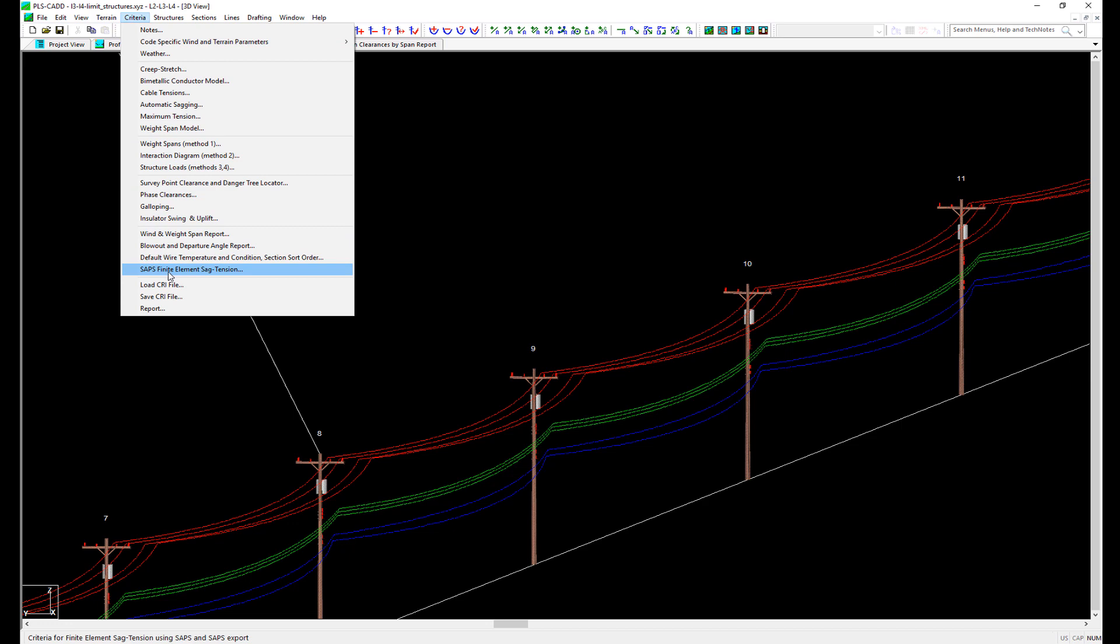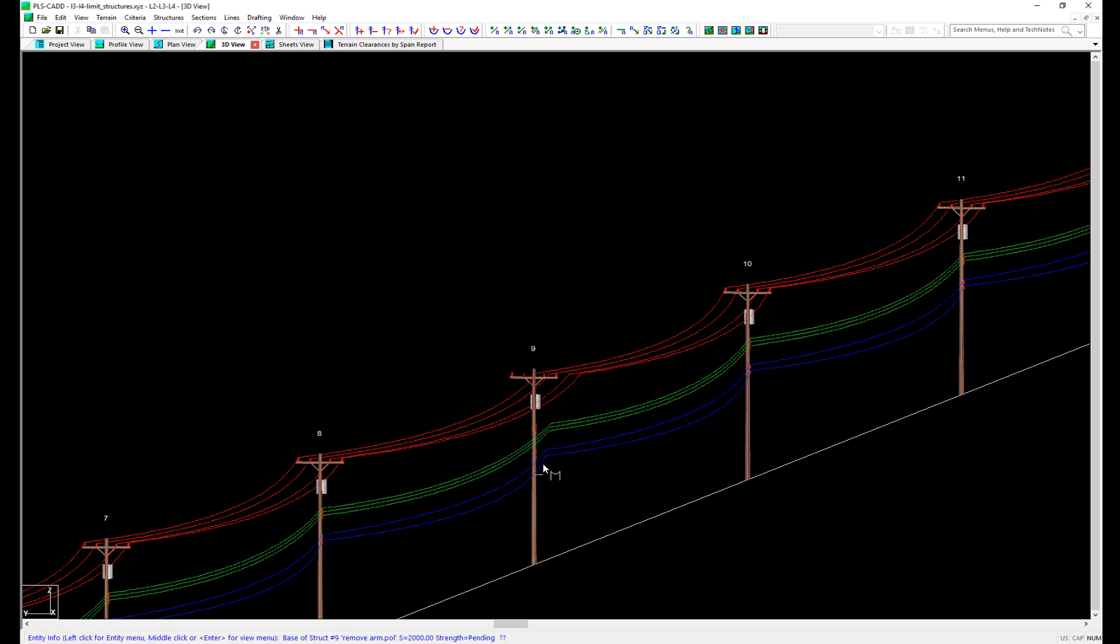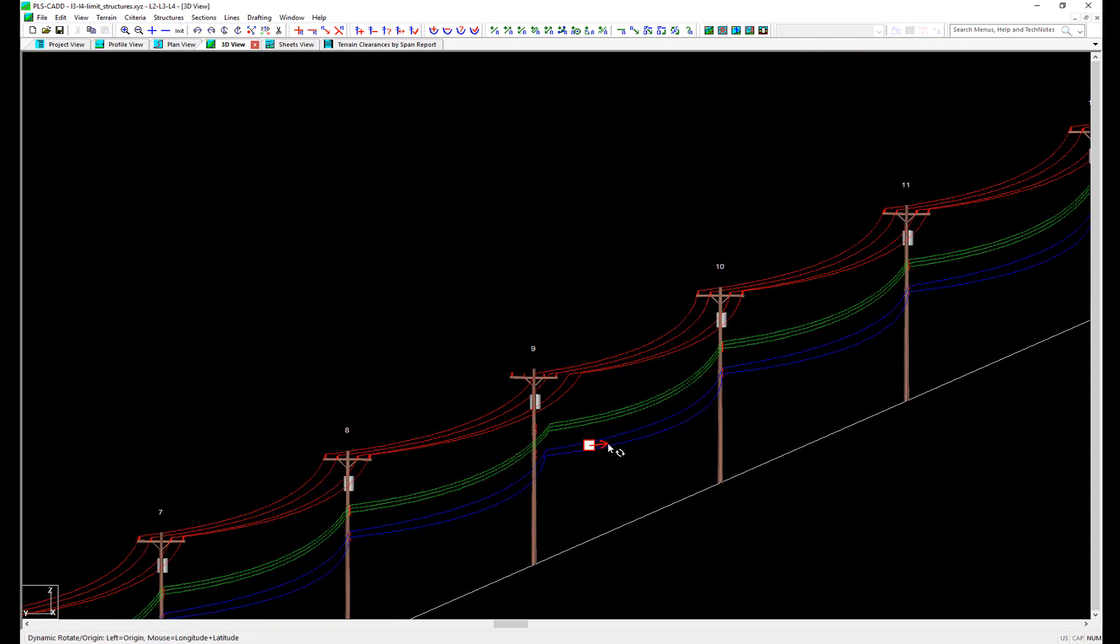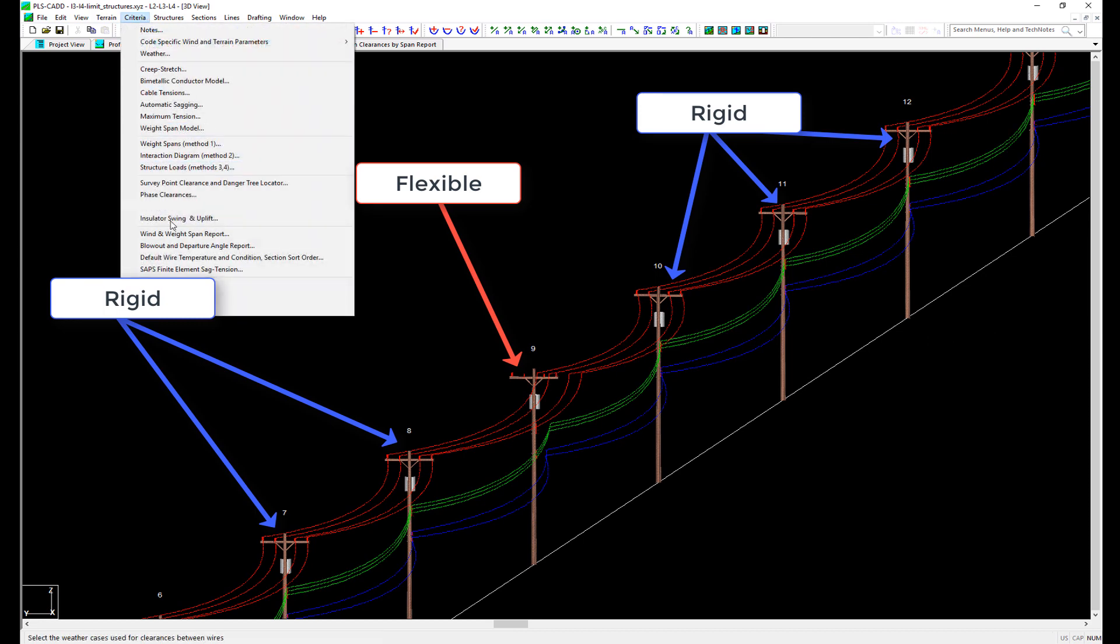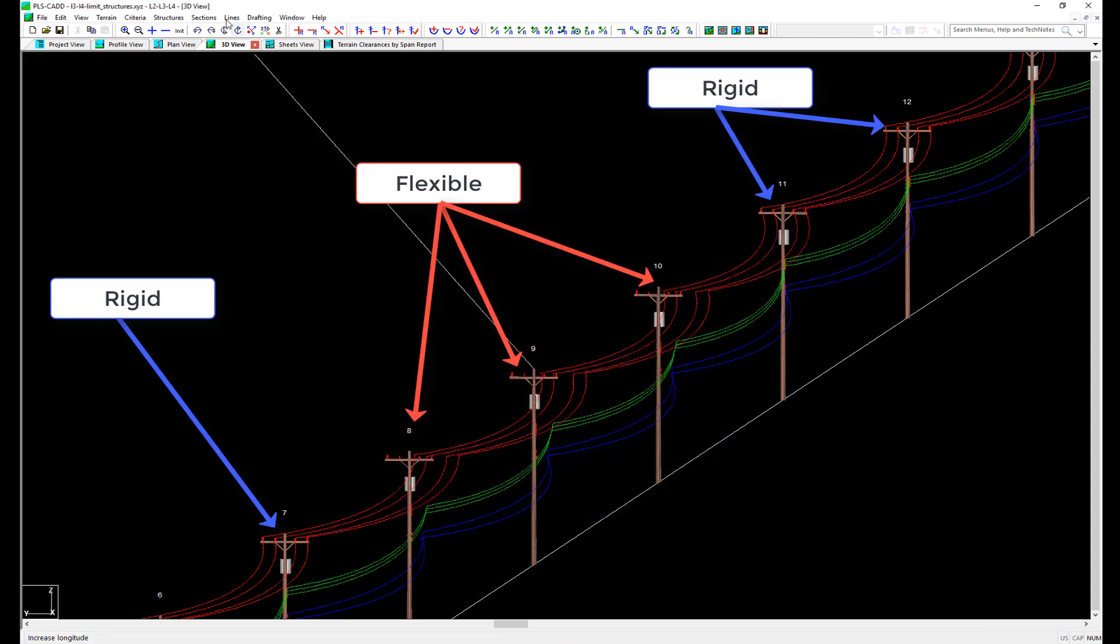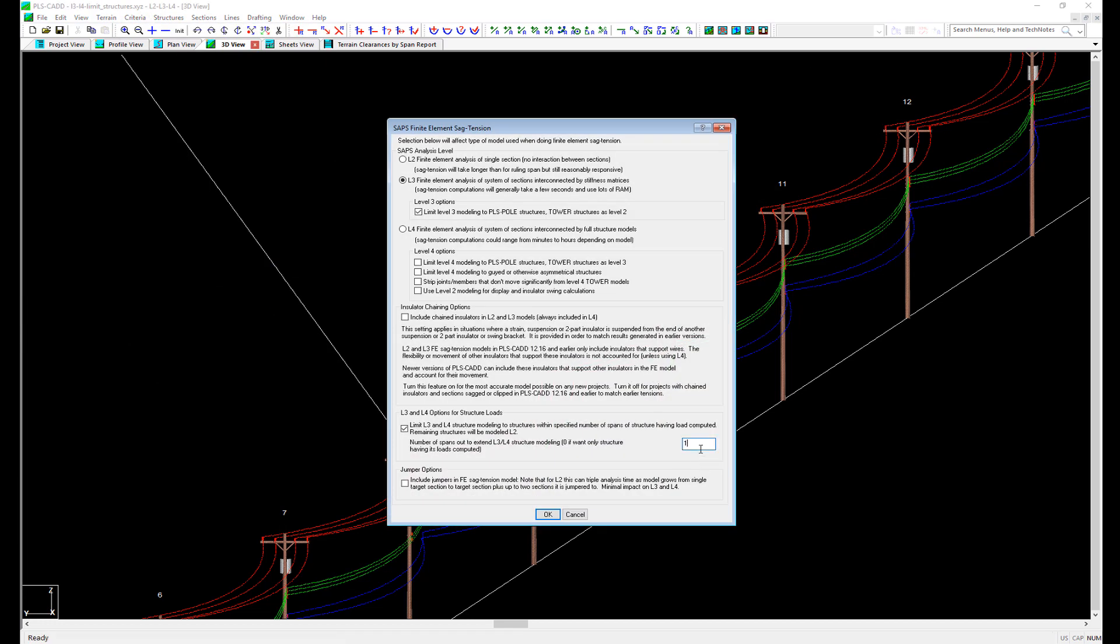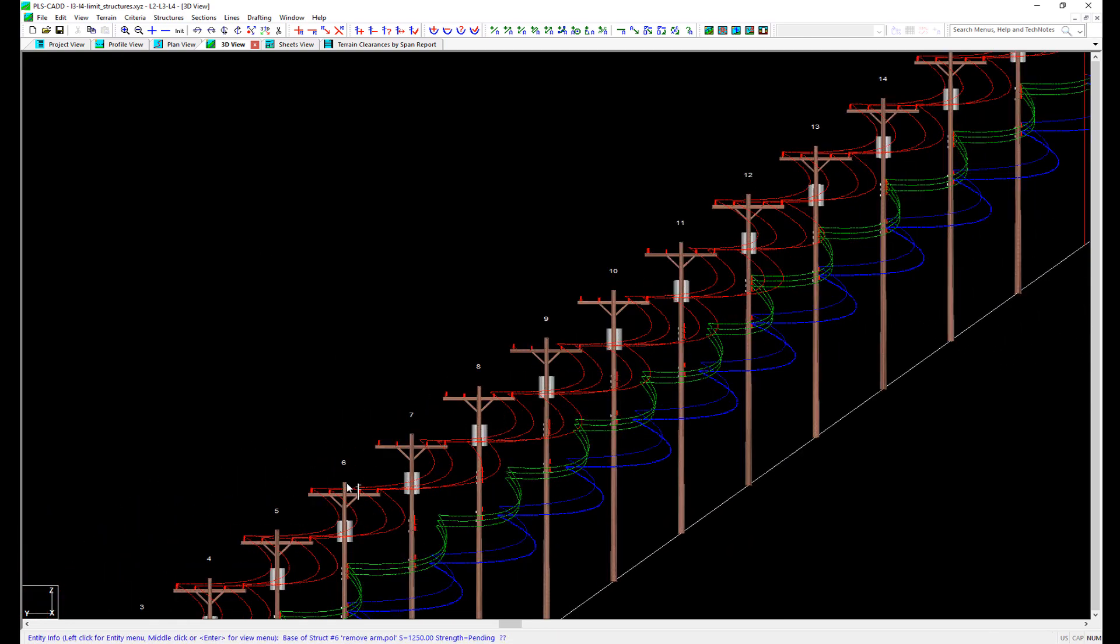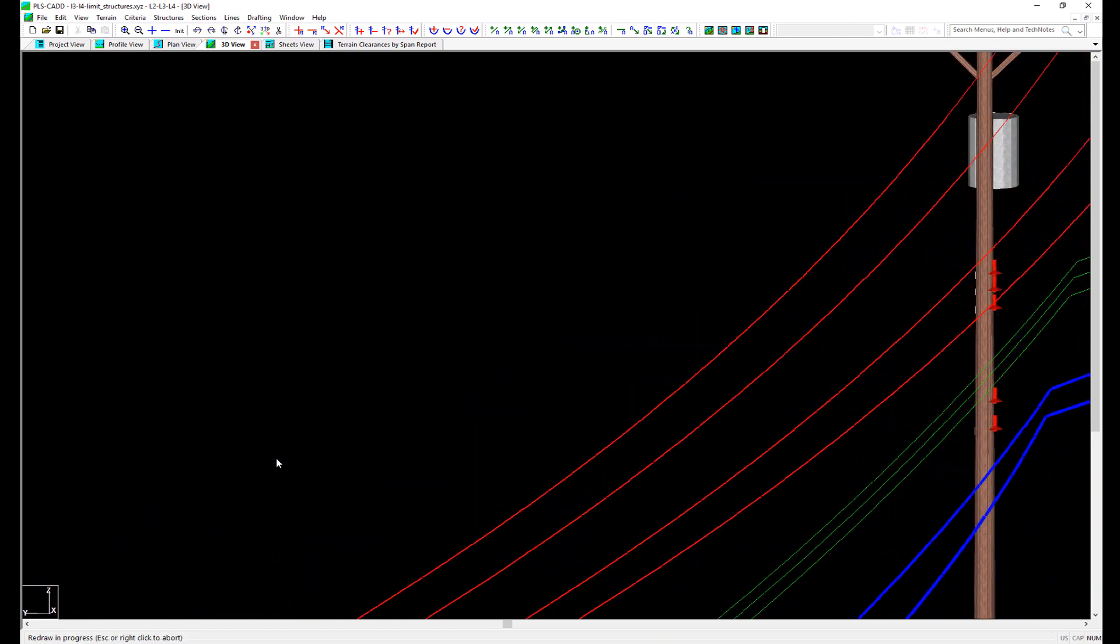There is also a feature in the SAPS criteria here to limit the number of structures to include in a L3 or L4 sag tension analysis. When we enable this option and leave it set to 0 and click OK, notice how only Structure 9 is the one that has deflection. All of the other structures are assumed to be rigid. If we go back and change it to 1, now structures 8 and 10 are flexible as well. And if we change it to 2, now structures 7 and 11 are also flexible. Using this feature can drastically decrease the time it takes to perform structure checks since the loads are calculated using a limited set of structures for deflection.